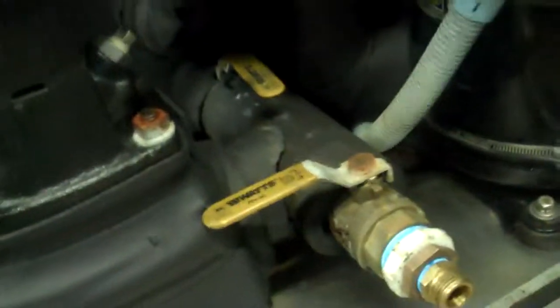Also, both sides of the unit, in addition to having this nice coil guard, have coils that appear to have an E-coat. They call it coating for additional protection outside. Inside here, this is just your drain if and when you need it. That's our sight glass here. In this case, it should be dark. You don't want it pink, which would show moisture. Everything looks good there. It's our dryer. It's our TXV valve in there.